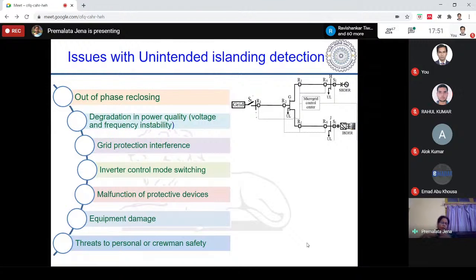This power quality issue means that when there's a power mismatch inside the microgrid after disconnection from the main grid, frequency and voltage variation occurs, and the inverter control mode switching may occur. The inverters used for solar, wind, or battery renewable sources take their reference from the grid side bus. When the grid side bus is not energized by the grid, the inverters may switch over to another control strategy, so those problems also arise.